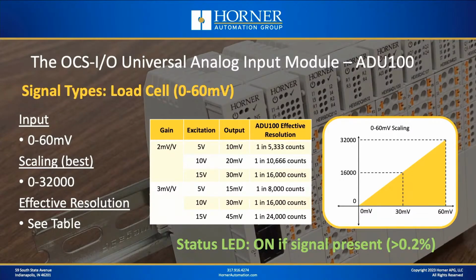Now, what is your effective resolution, though? So let's take a look at real-world applications with a couple of different load cells and, let's say, 3 different excitation voltage levels. A couple common load cell gains are 2 millivolts per volt and 3 millivolts per volt. And some common excitation voltages are 5 volts, 10 volts, and 15 volts. So in those scenarios, depending on your combination, you're going to get an output that ranges anywhere from 10 millivolts up to 45 millivolts. Again, depending on the combination of gain and excitation voltage.